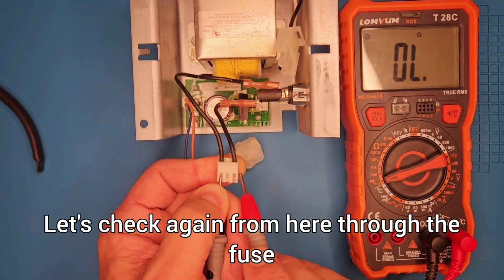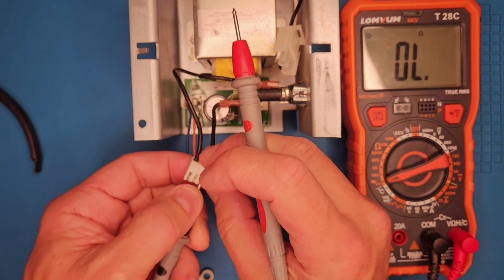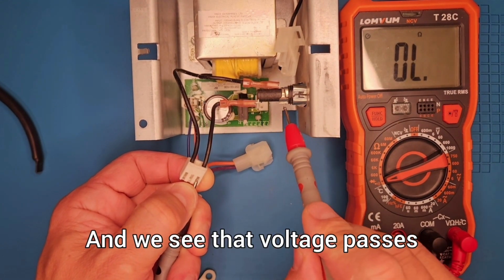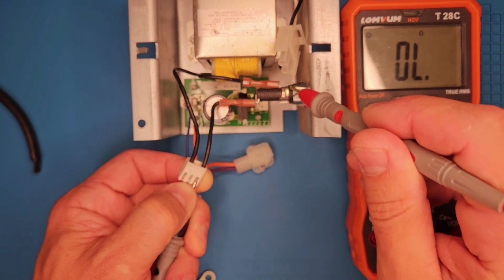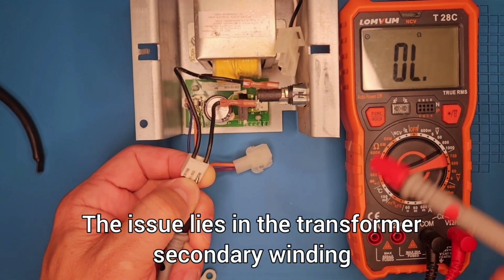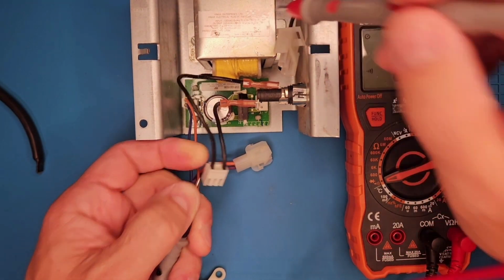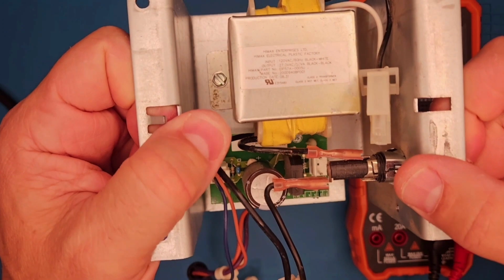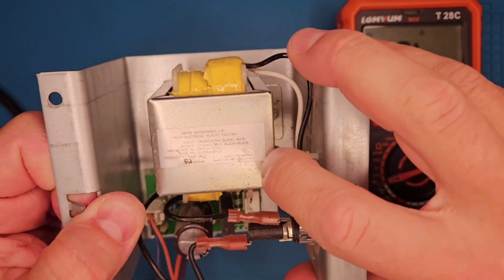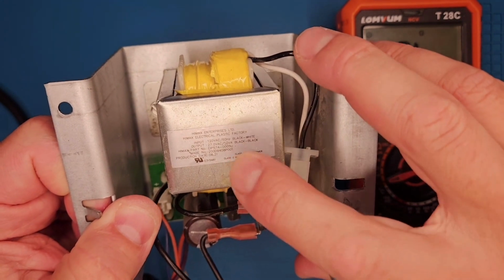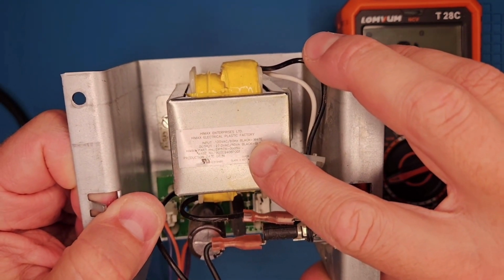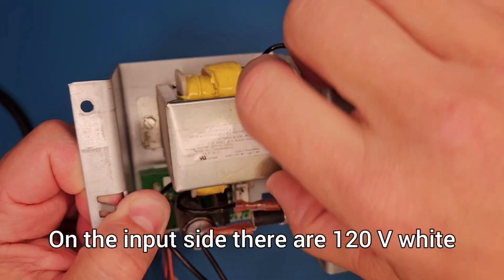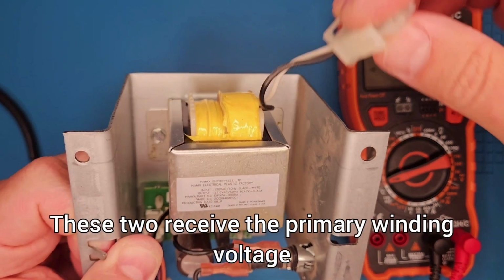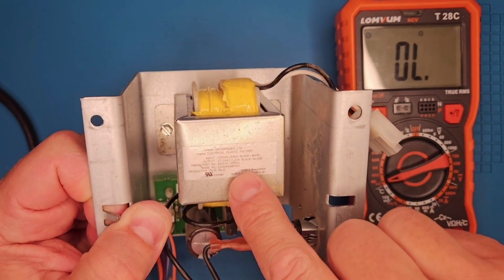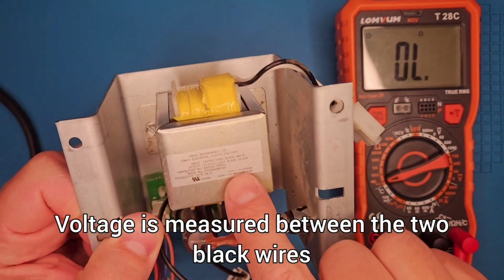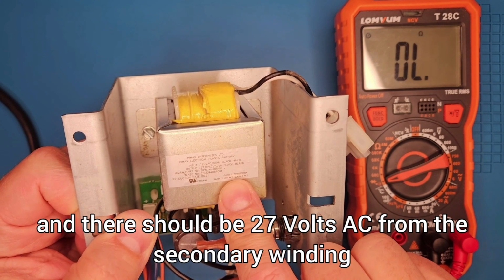Let's check again from here through the fuse. And we see that voltage passes. Conclusion: the issue lies in the transformer's secondary winding. There's a label on the transformer. On the input side, there are 120 V white and black wires. These two receive the primary winding voltage. Voltage is measured between the two black wires, and there should be 27 VAC from the secondary winding.